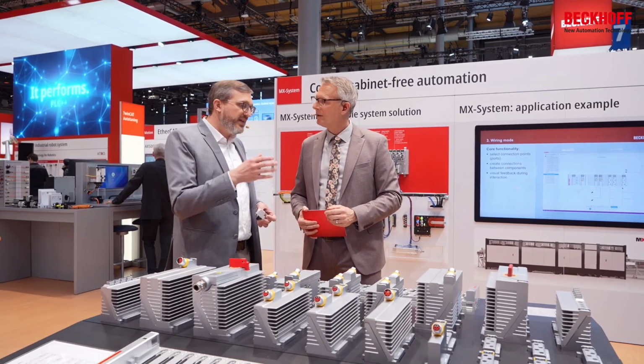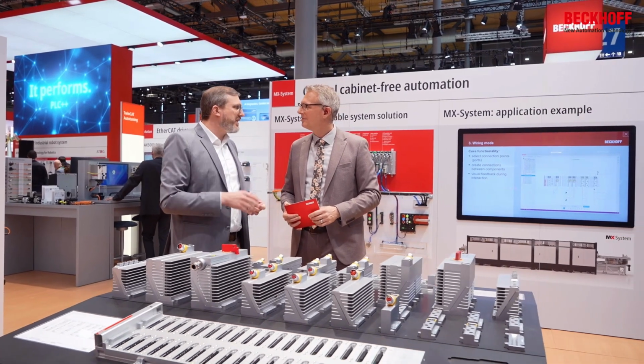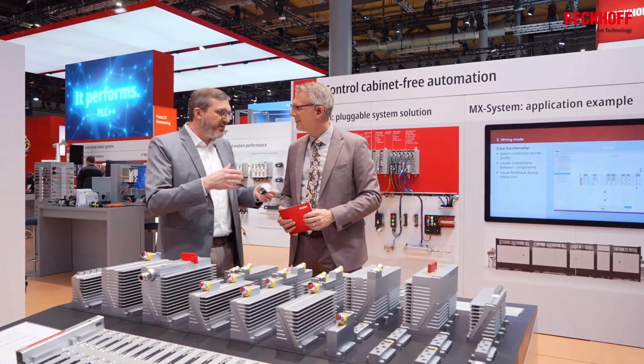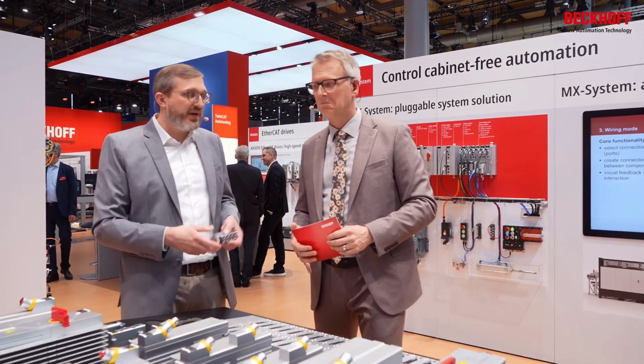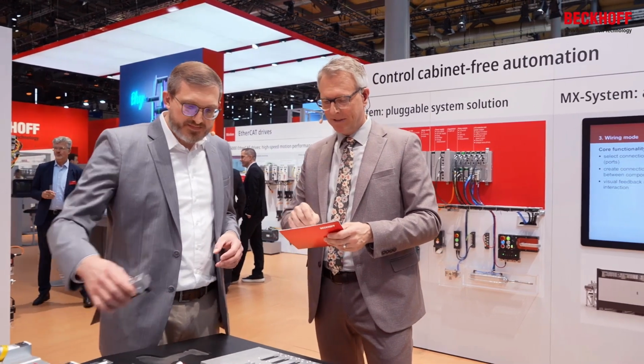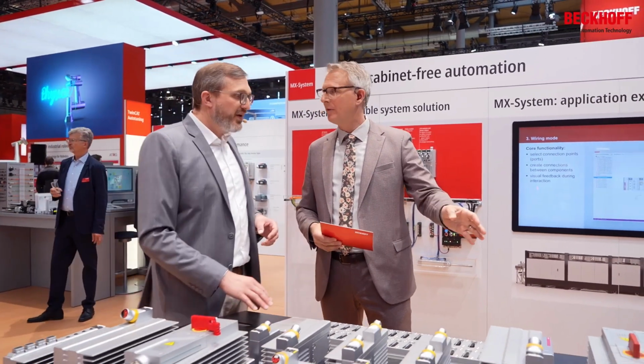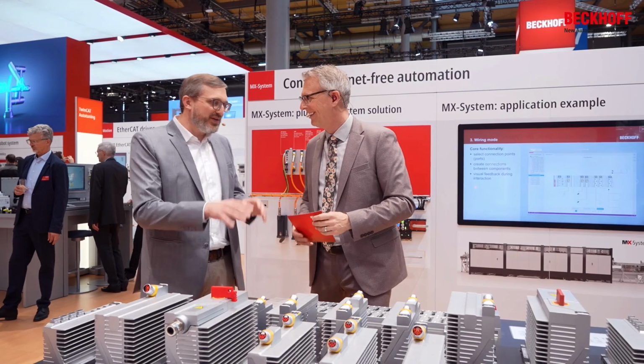So the designer can calculate the power consumption or the current consumption from each and every power supply. So let's say you have a lot of drives in there, and you would exceed the maximum power the power supply can deliver, and then the designer would give you a warning: that might be a bit too much here, you're using 150%. And then you can rework stuff, maybe put another power supply in it, and work with the feedback. So I don't need my notepad and say 5 amps, 10 amps plus 5 amps, like 20, and the power supply only at 15. This is done. This is all done in the designer, yes.